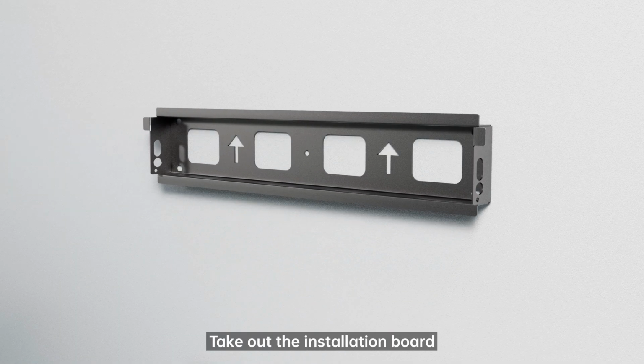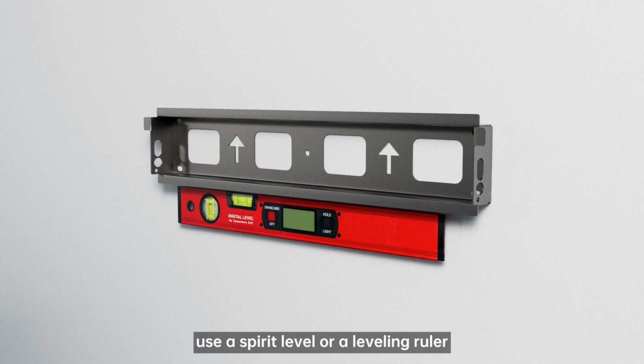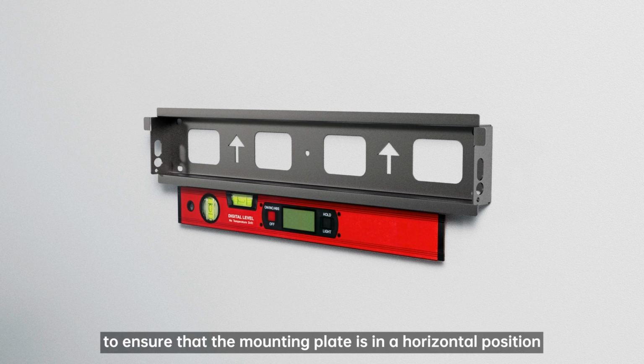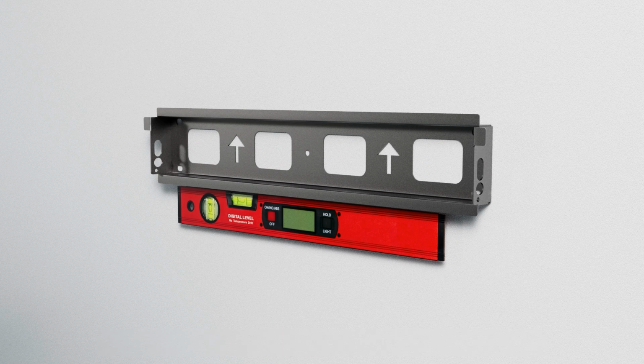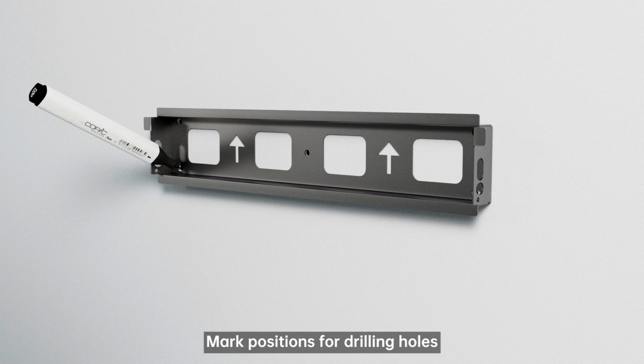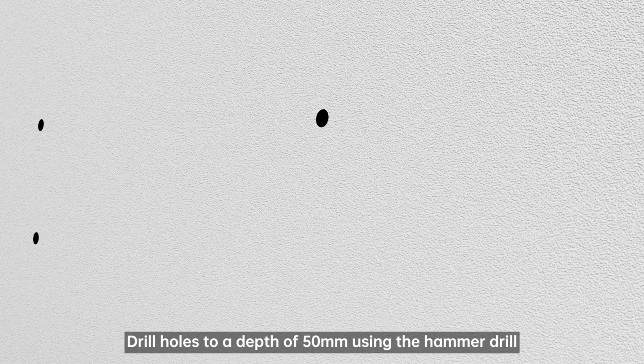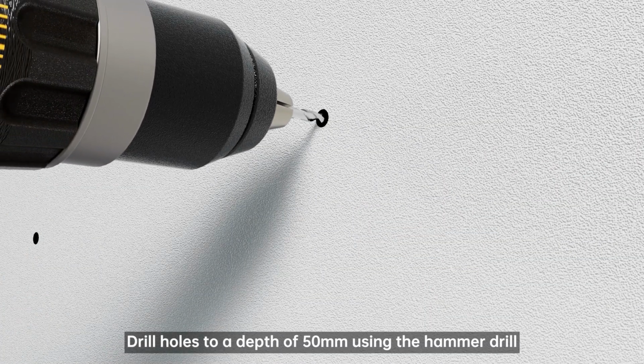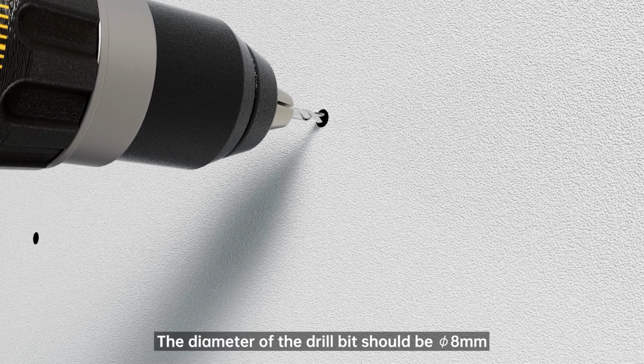Take out the installation board. Use a spirit level or a leveling ruler to ensure that the mounting plate is in a horizontal position. Mark positions for drilling holes. Drill holes to a depth of 50 millimeters using the hammer drill. The diameter of the drill bit should be 8 millimeters.